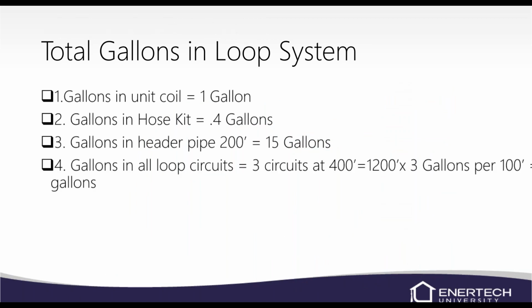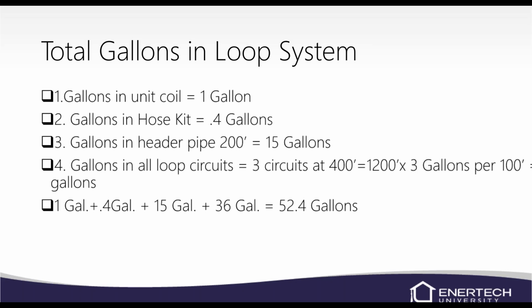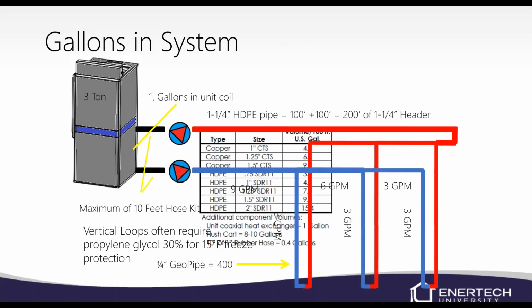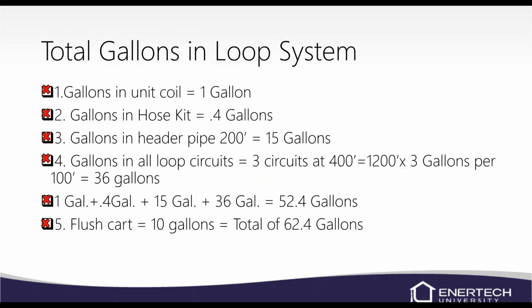So we have 1,200 total feet times 3 gallons per 100 feet. Looks like it cut it off there. But that would be, what, 40 gallons or so? 36 gallons. So we know we have 36 gallons in our verticals. We've got 15 gallons in our header pipe, 1 gallon in the unit, 0.4 in the hose kit, and we'll use probably the 10-gallon number for the flush cart. So we have a total of 62 gallons in the entire system. That's the total volume.